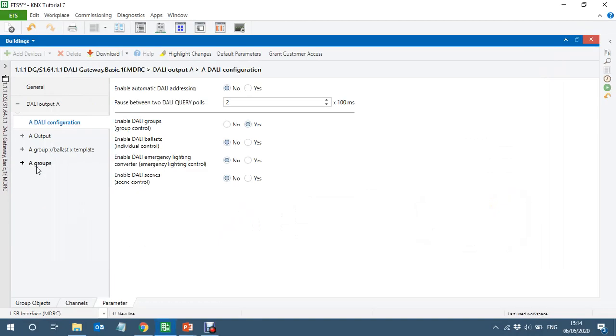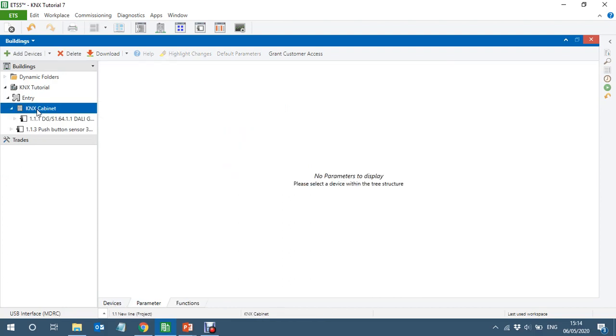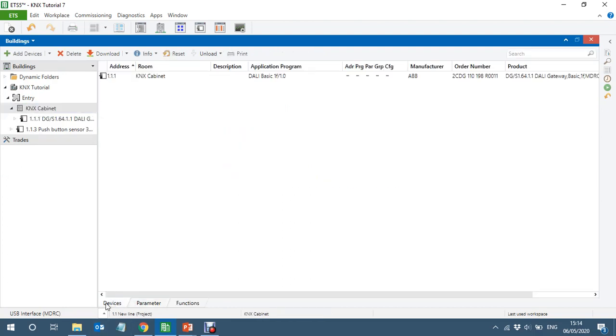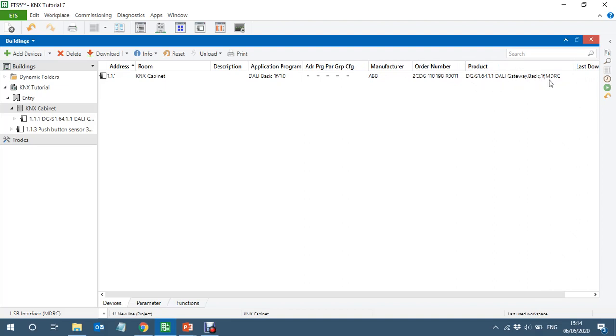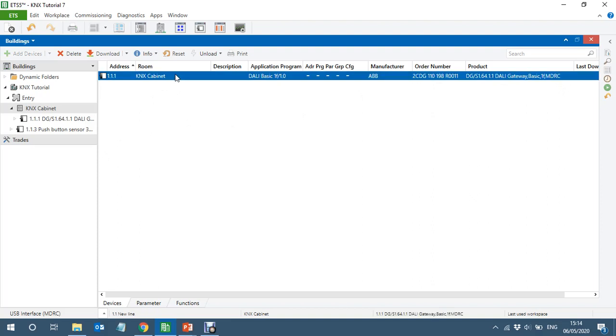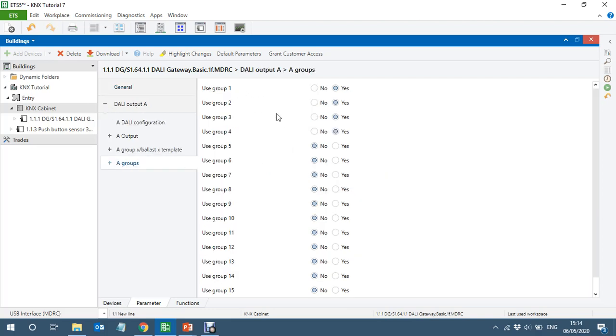So here I have already added this device. If you go to KNX cabinet, we have a device which is DALI gateway. Let's see, this is DG/S1.64.1.1 DALI gateway basic one MDRC. So this is one channel DALI gateway with one channel. You can have up to maximum, normal way you can have up to 16 groups. So if you go into the groups, you can see how many groups we have, one, two, three, and you can have up to 16 groups.